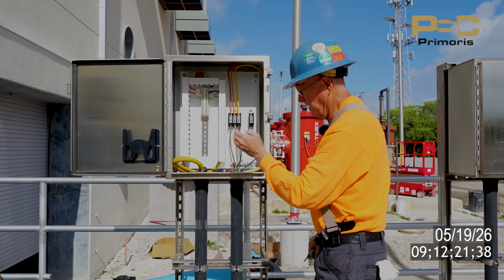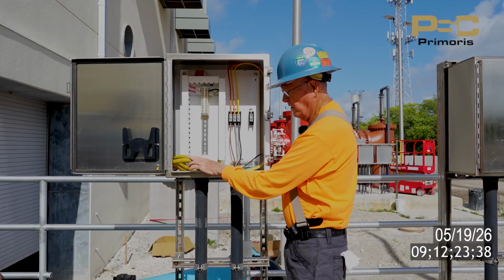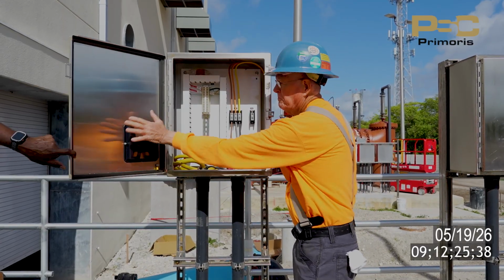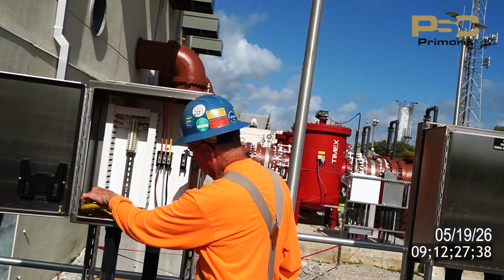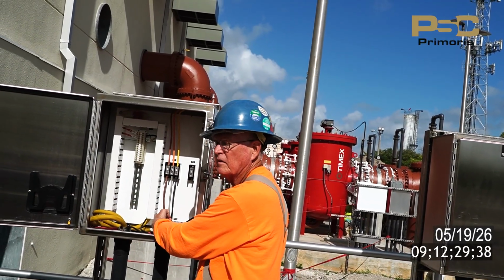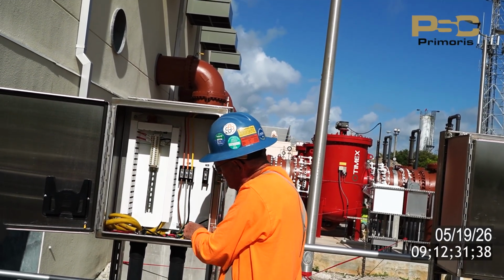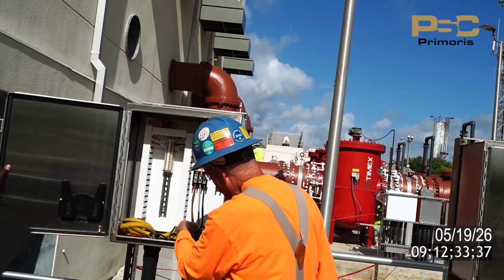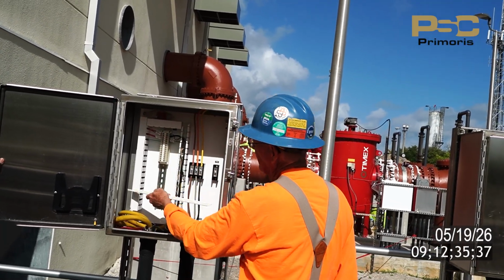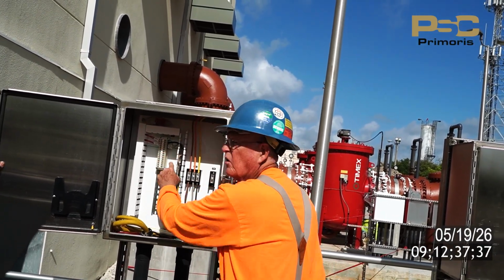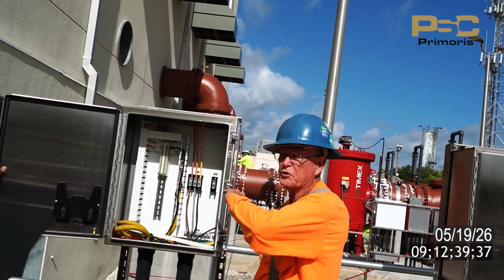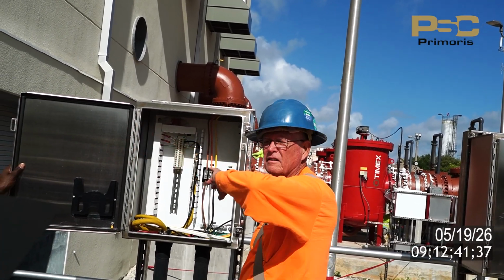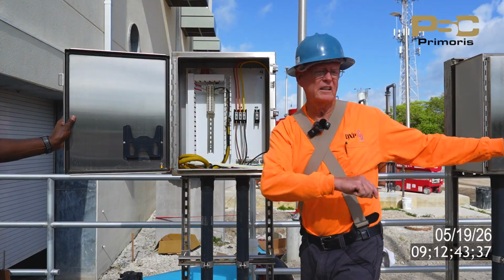So here's my cable coming up from the pump. I've got my power cable, which is the 3 leads of the motor and the big ground right here. And then I've got my control cable. The control cable comes up inside here and is landed on the terminal board. The drawing represents that back and forth, so on and so forth, and they're all identical.